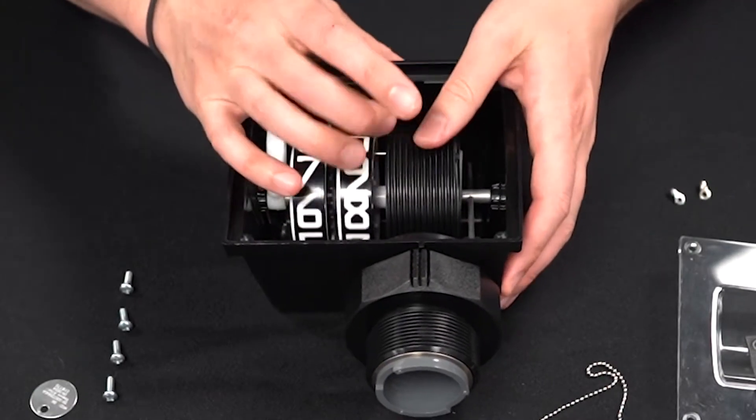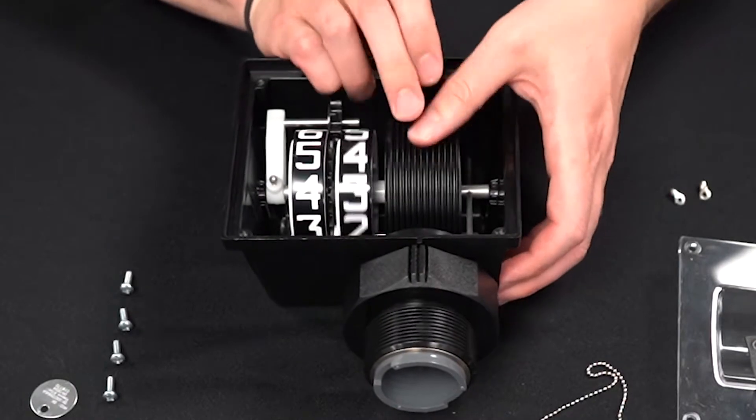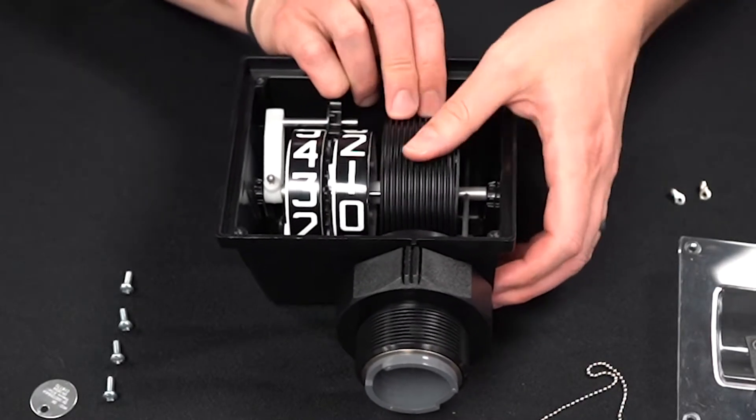Roll the pulley up until the numbers roll over double zero two times. This will create the correct amount of tension in the spring.